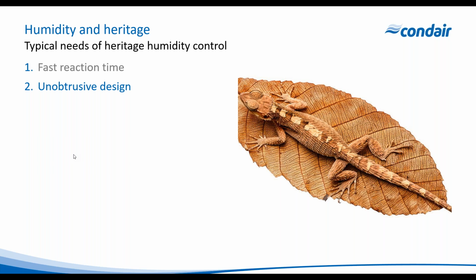If we're putting a humidifier in the space, we've got to have clearance around the unit so the humidifier can work correctly. There've been lots of applications where in-room steam generators have been used in museums, and the museum says, "Well, that's okay. We're controlling humidity very well, but I don't want to look at it." So there have been lots of applications where they've been screened and panelled in, and then problems occur as the units overheat because the humidifier should be ventilated. And also we need to ensure that there is clearance around the humidifier for steam to be absorbed into the air if we're using a steam system.